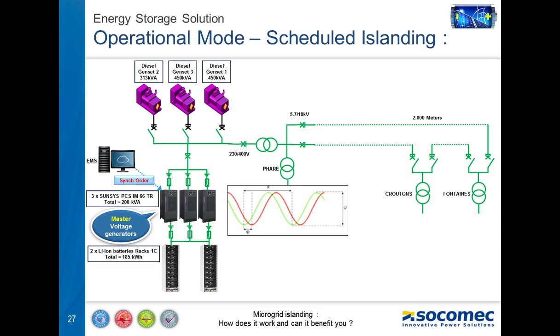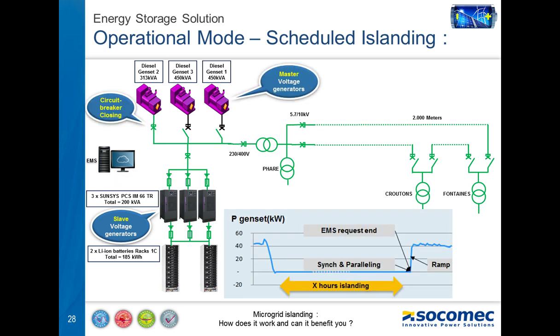Then, when the EMS forecasts or detects a lack of PV production or a low battery state of charge to supply the load, it can ask for the genset reconnection. From this situation, the genset is started, and once the nominal speed and voltage are reached, the EMS asks for the synchronization sequence, either done by the genset or by the PCS. The target of this sequence is to ensure the perfect alignment between genset and energy storage voltage, frequencies, and phases.